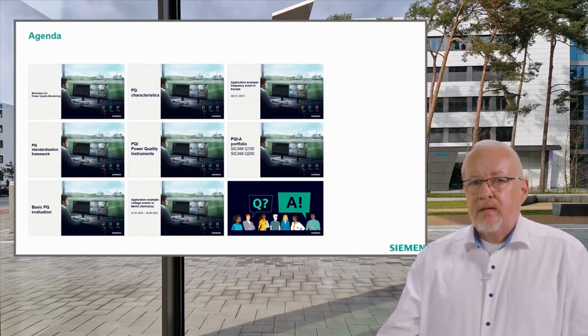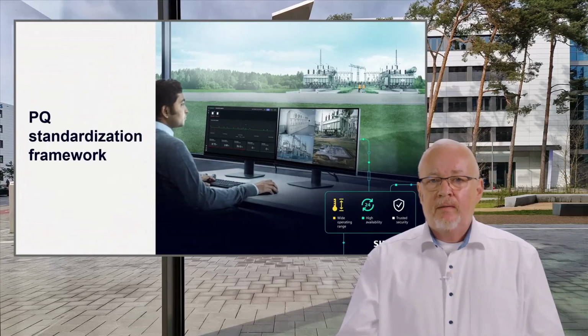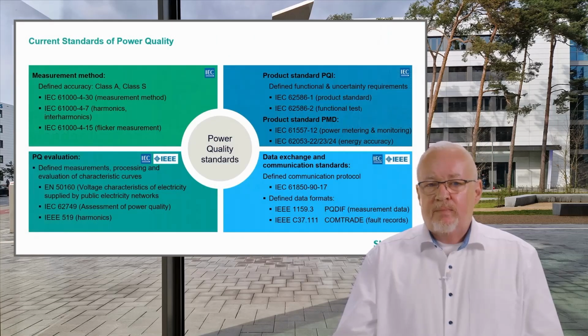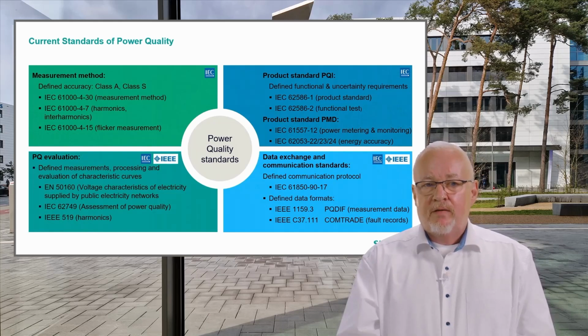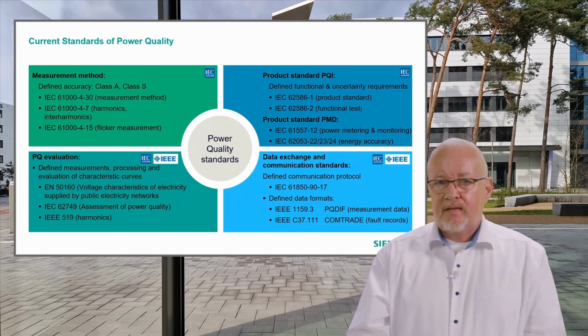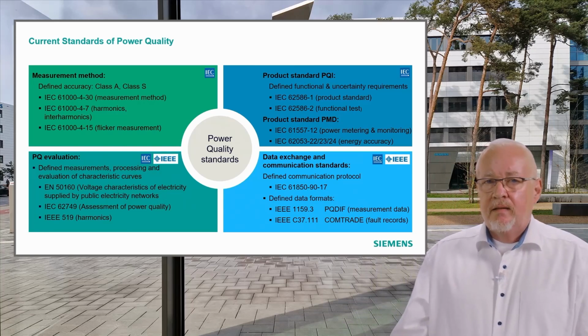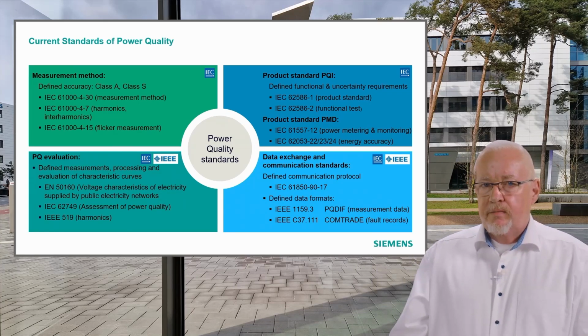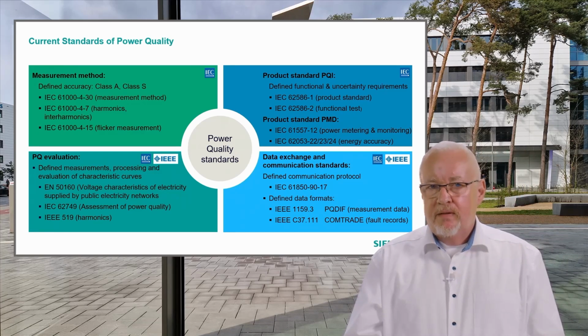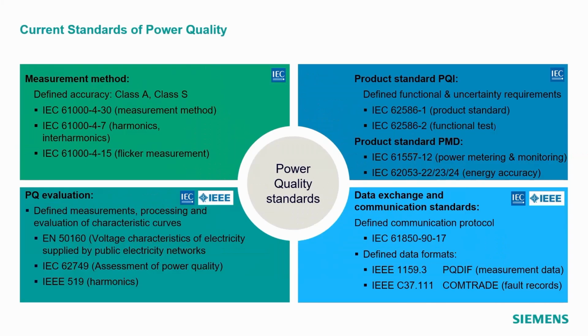So let's go on with the power quality standardization framework. You see that the power quality standardization framework consists of 4 blocks. Block 1 are the measurement methods. The leading standard is IEC 61000-4-30, where the measurement methods are defined. We are working on edition 4 at the moment. Edition 3 from 2015 is still valid. The standards referenced there are 4-7 for harmonics and interharmonics and 4-15 for flicker measurement.